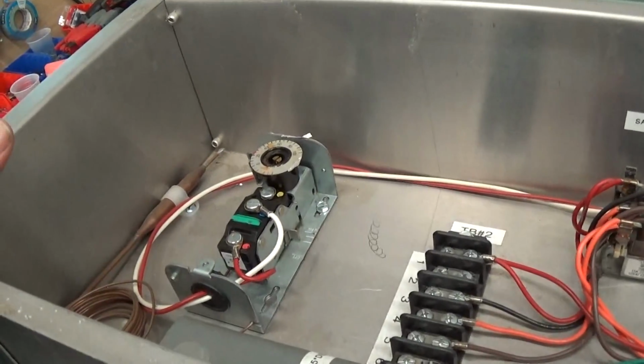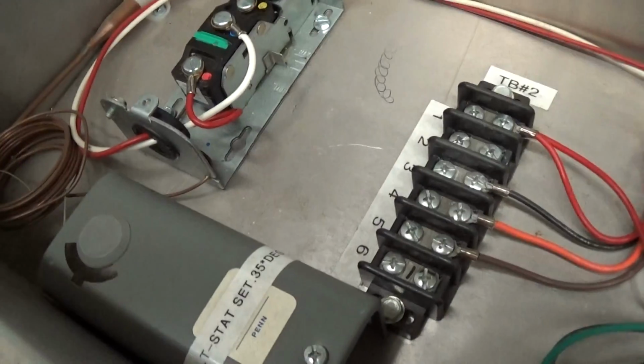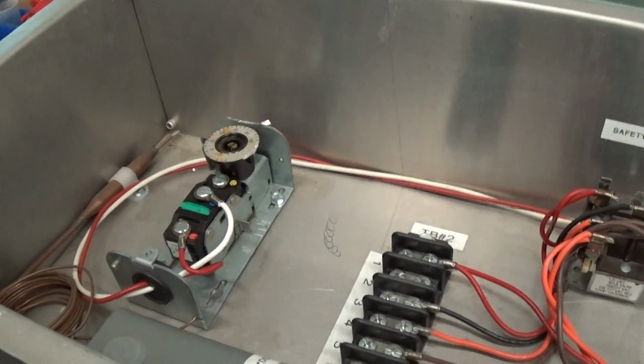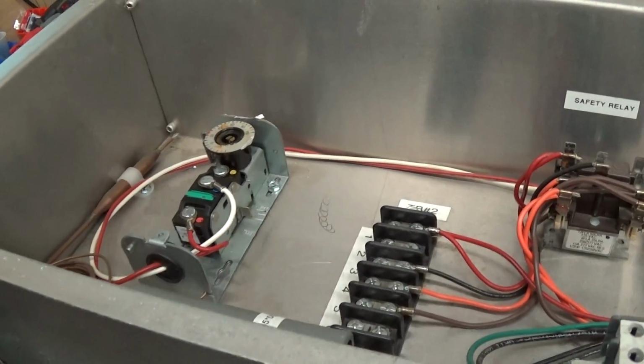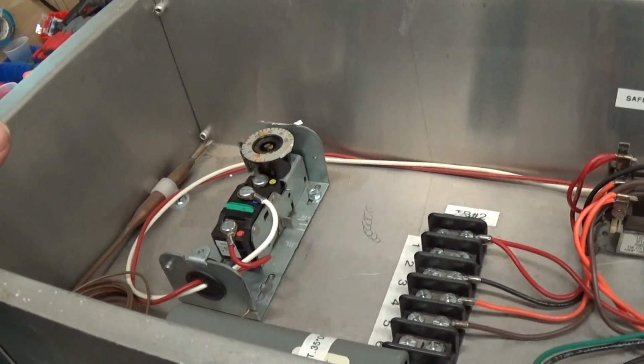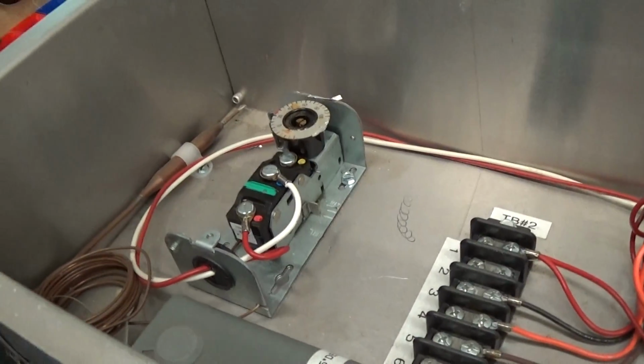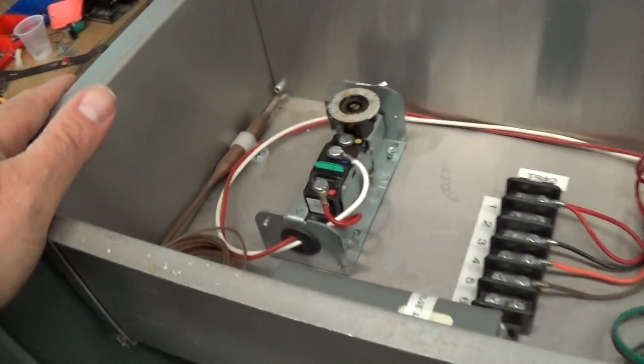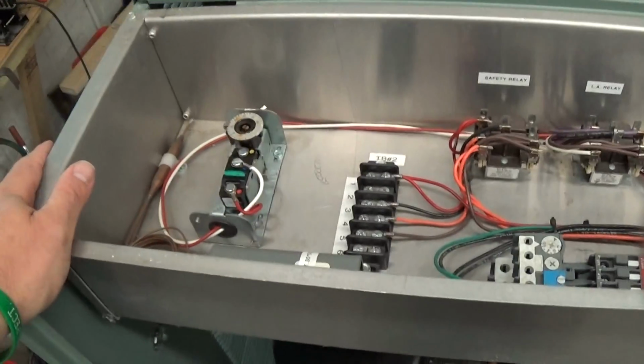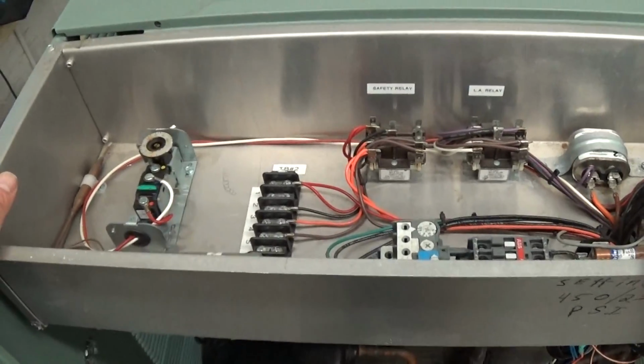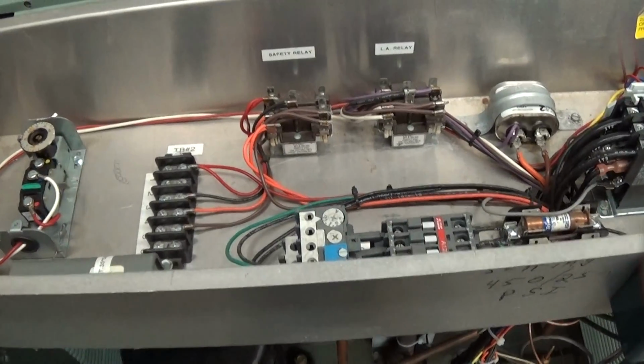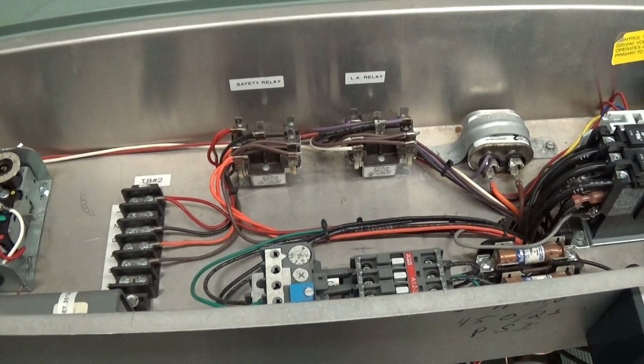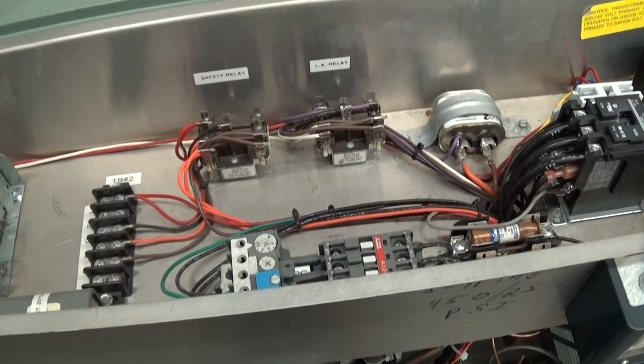We have a freeze-stat in the unit. We'll preset that. The cover's not on right now. That's a safety device. We're going to preset that based on the fact that the customer is going to run to 30 Fahrenheit. You'll hear that click, by the way, and the fan just turned on. That'll be set at the appropriate temperature, based on the fact the customer should be running about 40% glycol, as related to a 30-degree Fahrenheit process temperature.